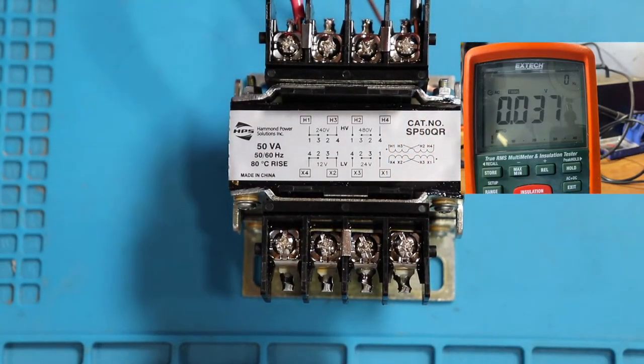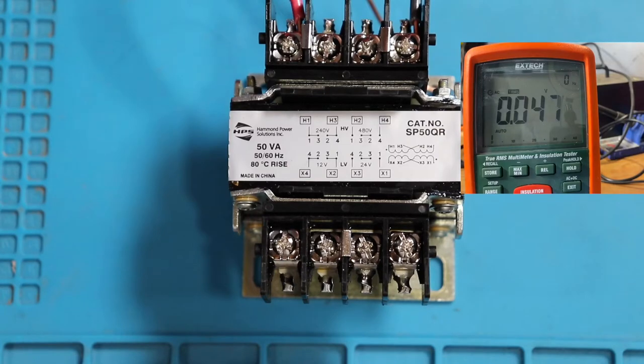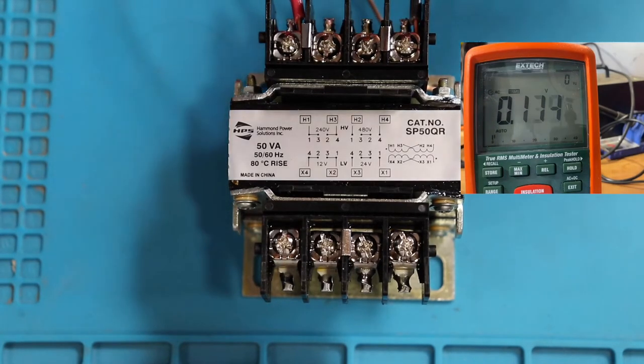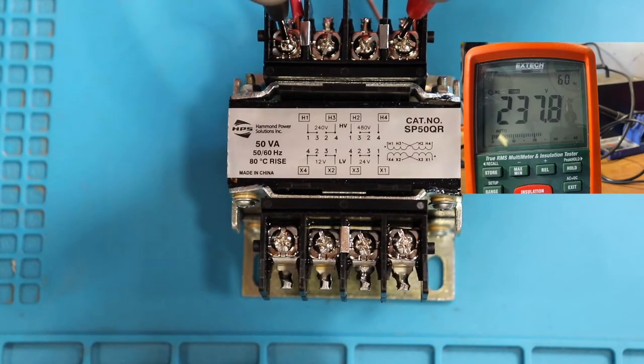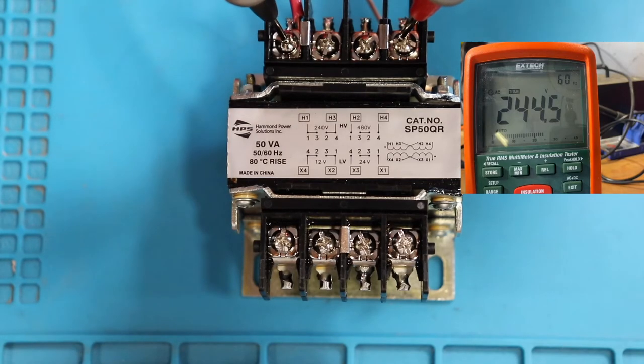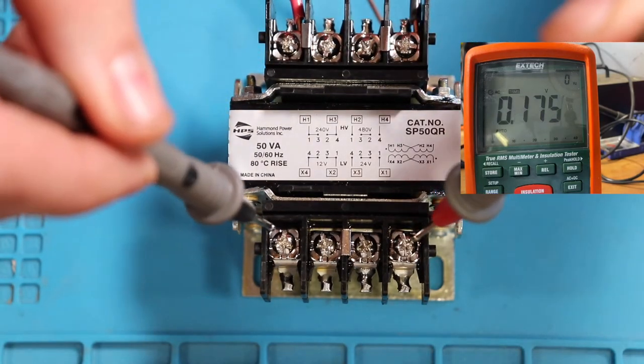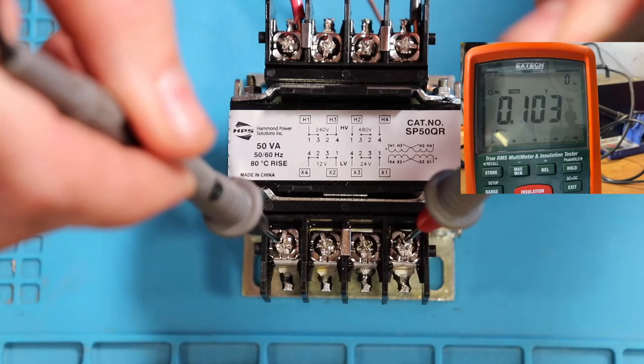Now that our 24 volt tap is in place, we can turn the power back on and test out our voltages. Again, we'll test our primary just to make sure we have the proper incoming voltage. That's good. And now to test for our 24 volts, the same points as the 12 volts.